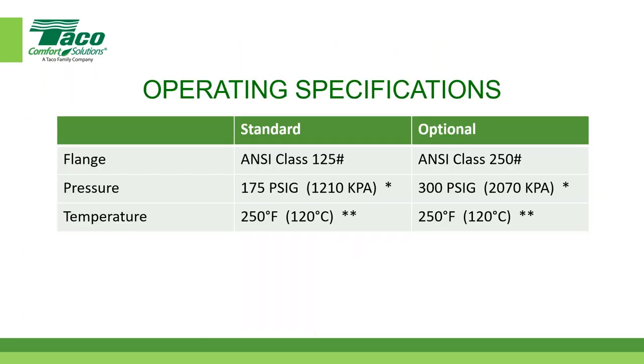I forget. So here are some operating specifications of the FI and CI pump. First off, the flanges. You rate these pumps by flange ANSI classifications, so you can get 125 pounds or 250 pounds. If you have a high rise or higher pressure project, you might want that ANSI 250 flange for the bigger ones. But to be quite honest, for the most part, most of ours going through the facility on a daily basis are 125 pound. Pressure ratings are a little higher there. You can see 175 PSIG, or you can get an optional 250 flange with a 300 PSIG rating.